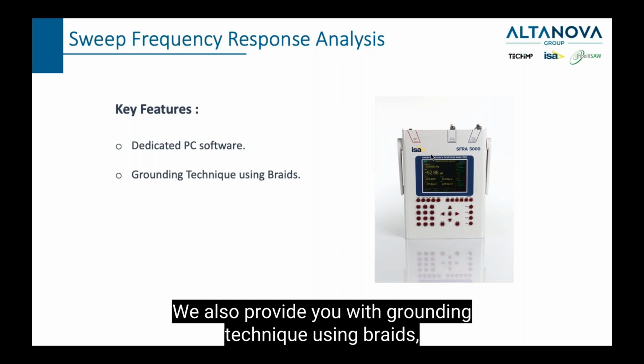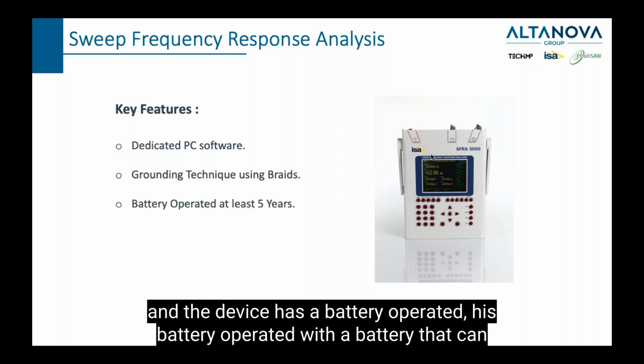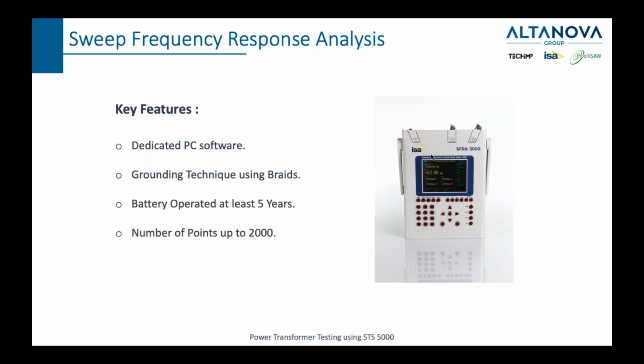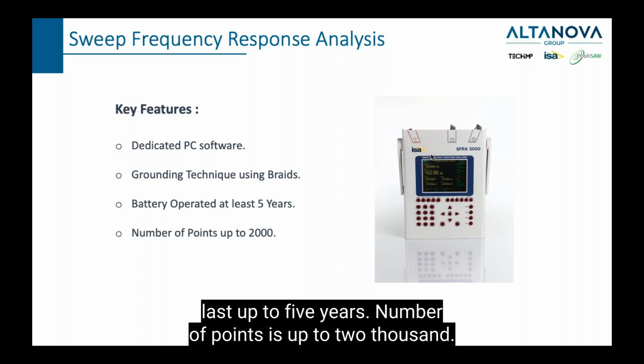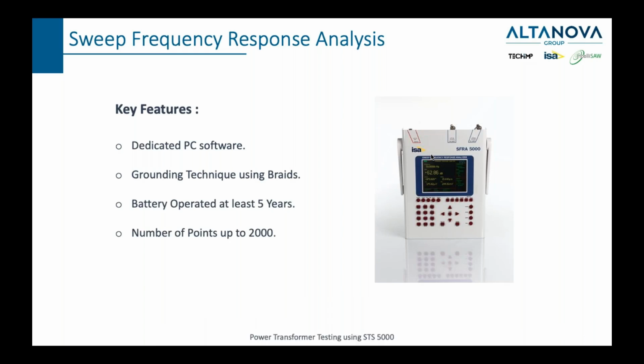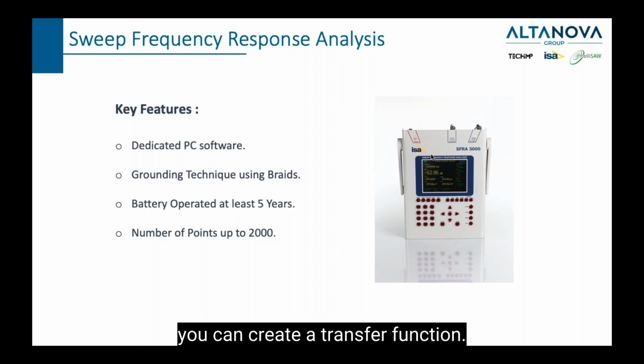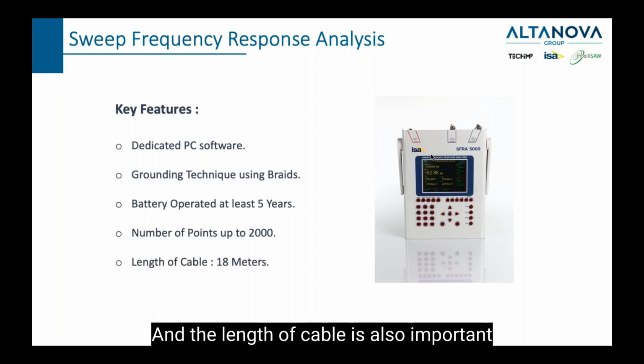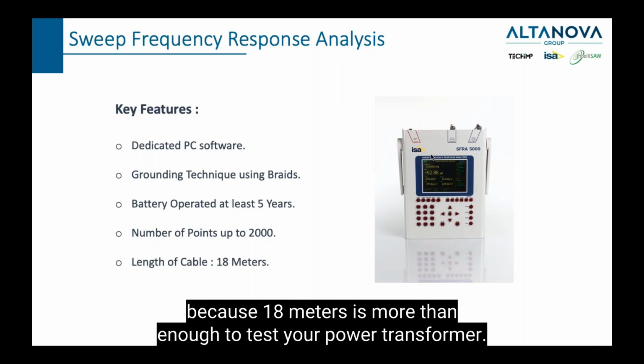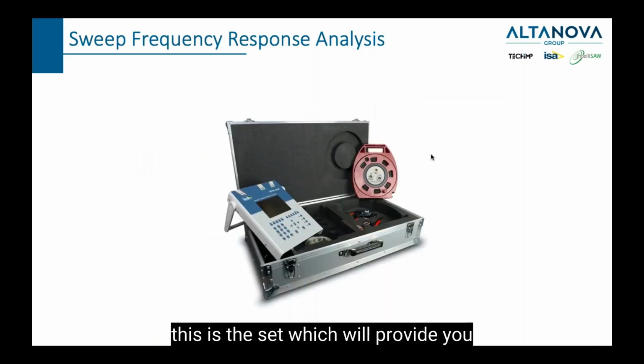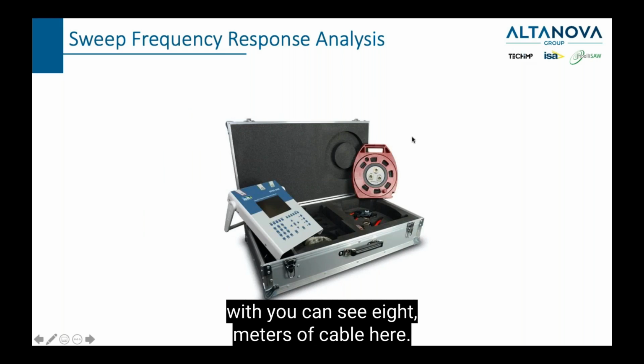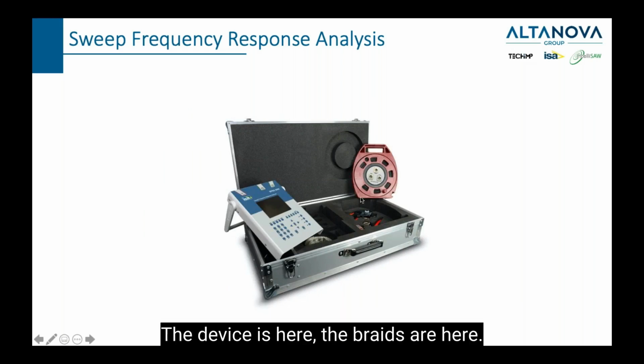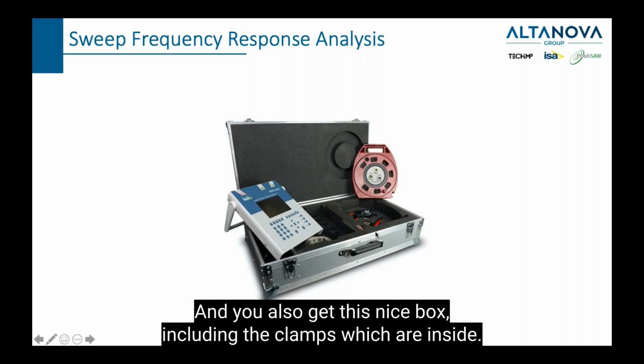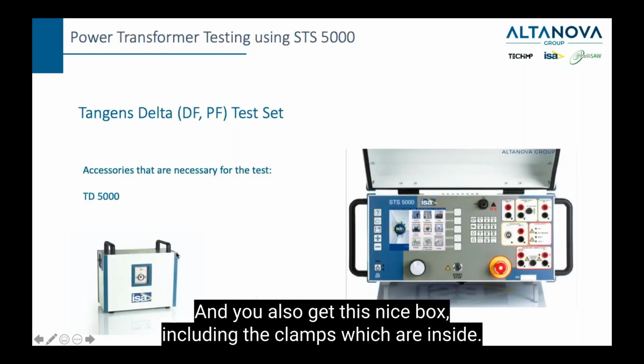We also provide you with a grounding technique using braids, and the device is battery operated, with a battery that can last up to 5 years. Number of points is up to 2,000. So for 2,000 points, you can create a transfer function. And the length of cable is also important because 18 meters is more than enough to test your power transformer. So this is the set which we provide you with. You can see 18 meters of cable here, the device is here, the braids are here, and you also get this nice box including the clamps which are inside.